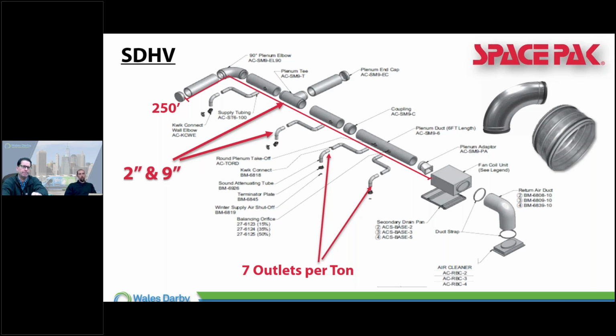Yeah, you might have to add quite a few outlets. That's so correct. More times than not, what we've seen inherently is that noisy system, and it's pretty quick to figure out. Not even talking about lengths of the 2-inch yet, just how many outlets, and why are you 8 short for this air handler size?